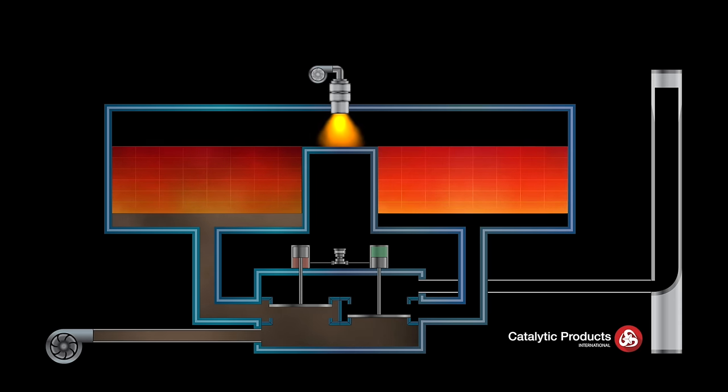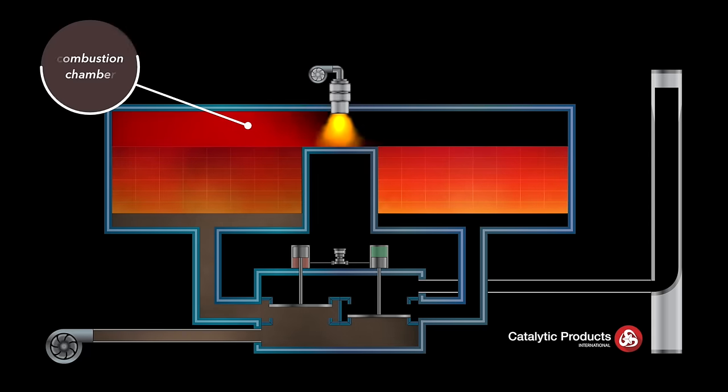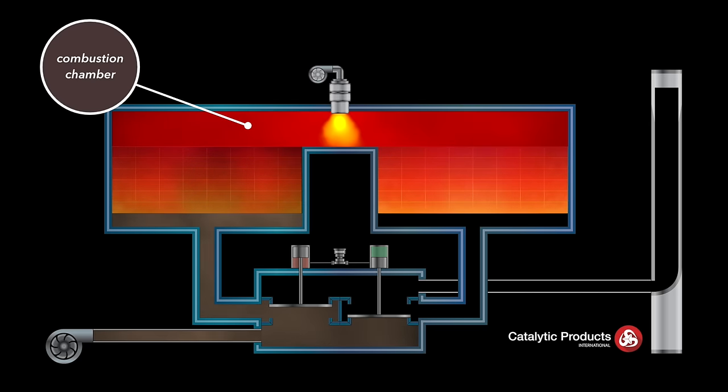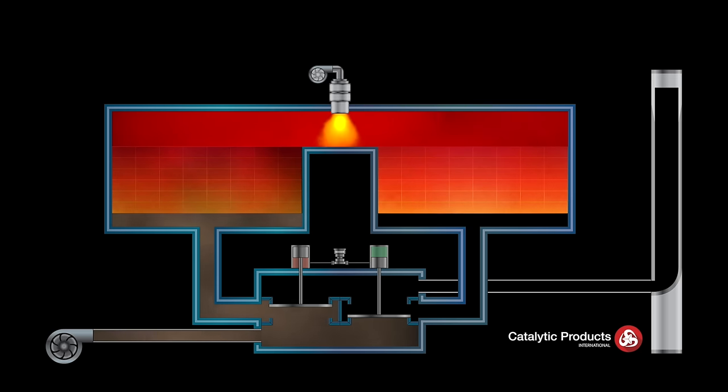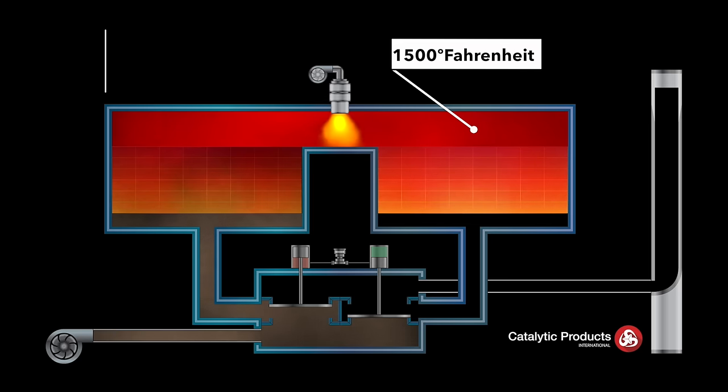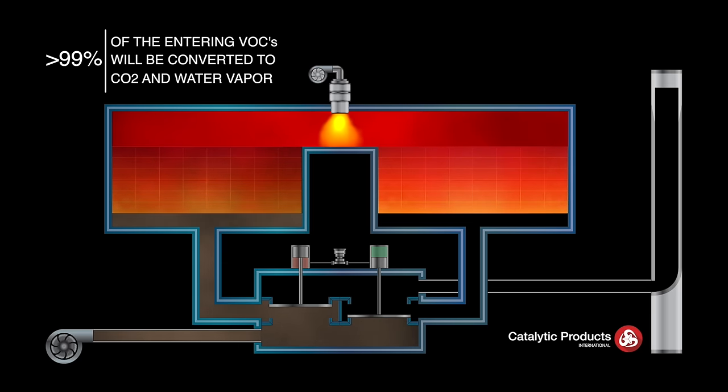The preheated process stream then enters the combustion chamber where the temperature will be raised to the set point where oxidation of the VOCs is completed, typically around 1500 degrees Fahrenheit. At this temperature greater than 99% of the entering VOCs will be converted to CO2 and water vapor.